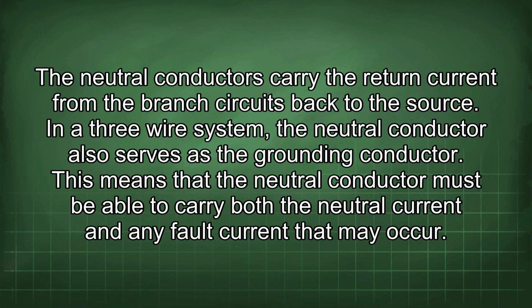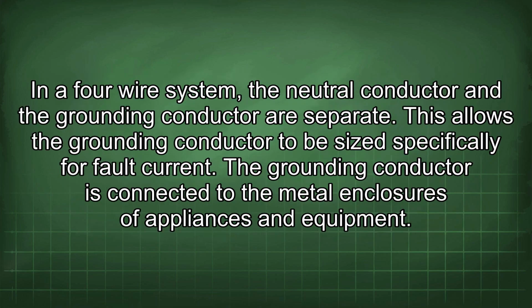In a 3-wire system, the neutral conductor also serves as the grounding conductor. This means that the neutral conductor must be able to carry both the neutral current and any fault current that may occur. In a 4-wire system, the neutral conductor and the grounding conductor are separate. This allows the grounding conductor to be sized specifically for fault current.